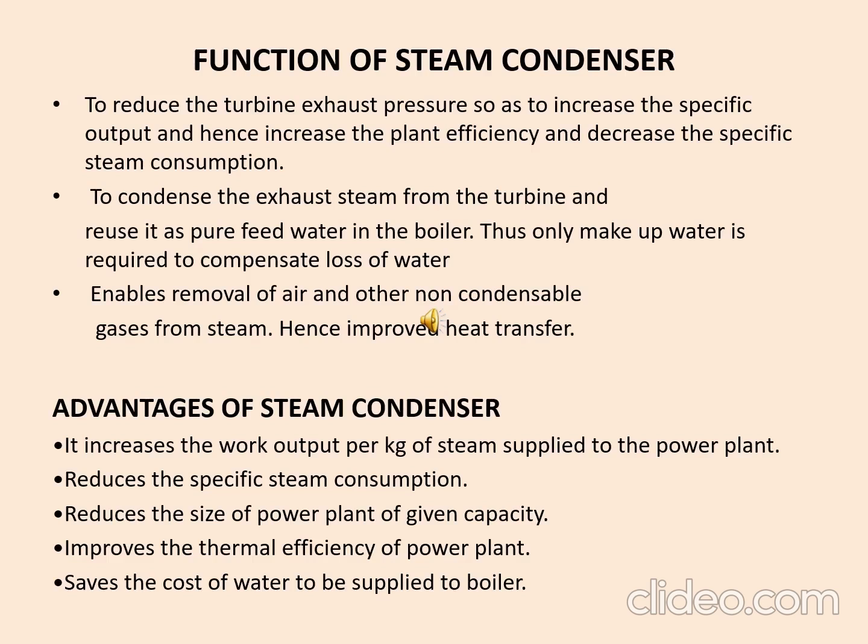Another function is that it can create a vacuum by condensing the steam. It can also remove unnecessary things like air and other non-condensable gases from the steam, so that better heat transfer can be achieved. Then it can provide a leak tight barrier against air, which can prevent excess back pressure on the turbine. So these are the functions.